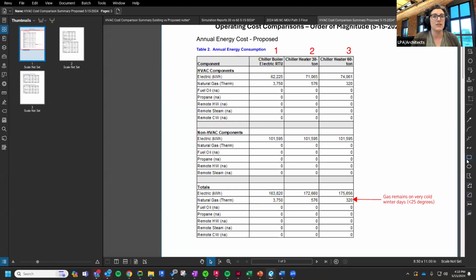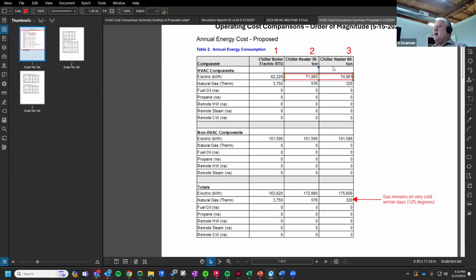And I just wanted to also mention that the difference in the electrical between the 30-ton and the 60-ton is very close. That kind of surprised Eric and me, but you explained it well to me, Kevin: the chiller heater is going to be working all the time, especially when it's in heat mode, right? So it's not going to make a huge difference. Yeah, on the cooling side, the 30 and 60 ton will probably use about the same power in cooling mode because we only have 30 tons of cooling load. So we'd only be running the 60 ton at half capacity. And then when we go to the heating mode, the 30 ton will cycle down to about 25 degrees and then it'll run continuous, where the 60 ton would run at maybe 40 tons of equivalent load.